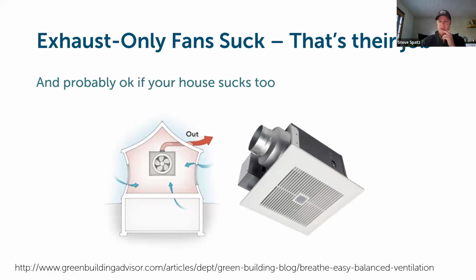So the reason we're getting to this point is, the idea of going from exhaust only to balanced is when you have exhaust only fans in the building, you're hoping and relying on air leakage through the building assemblies to be making up your fresh air intake, essentially. And we are not at that point anymore. If you're building a code compliant house at this point, the ACH numbers that are required to be met really are eliminating most of any passive air leakage through the building envelope. So if you do have exhaust only fans working in a tight house, you're often depressurizing the building, and you're really not getting good, effective fresh air intake into the building. And you're also really not circulating air and moving air around the building.